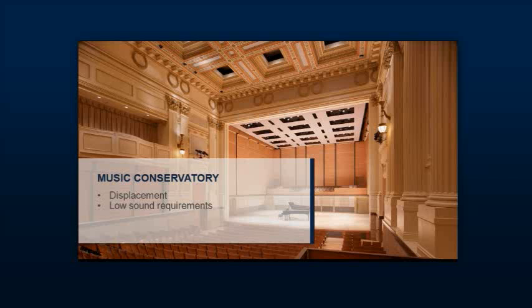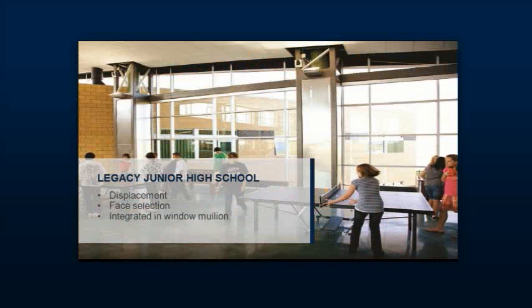So one of the questions that we had to resolve and found quite interesting results on was, will people be aware of the fact their feet are on top of diffusers, particularly women? I'm not trying to pick on them, but they typically wear more open-toed shoes than the men. And being as there's nothing between them and the diffuser, will they notice? The answer is some will, but a majority of them will not. Now, in our building goal, of course, is we want at least 80% of the occupants to consider the space thermally comfortable, and we achieve that very readily.